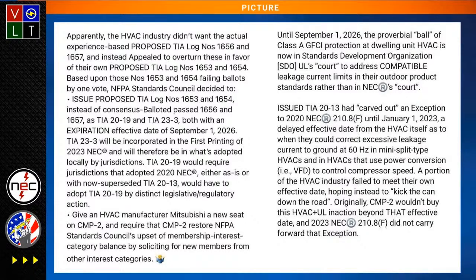What caused this in the first place? Code-making panel 2 decided that we needed GFCI protection based on one death. That's what it was all based on. And it was a very tragic death. Let me get into that. It was a tragic death, but things like that happen. But it wasn't based on GFCI protection not being provided. What it was based on was an improper installation.